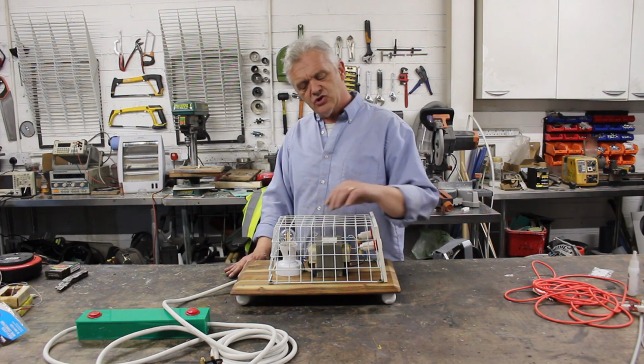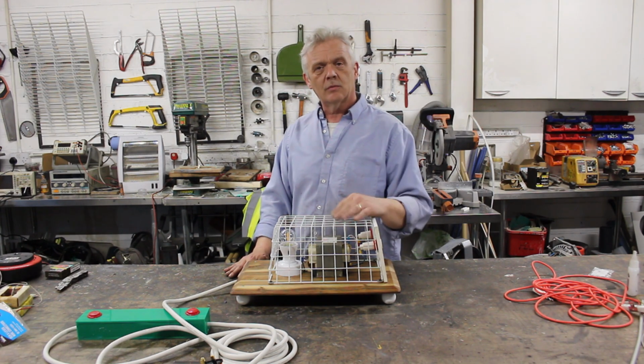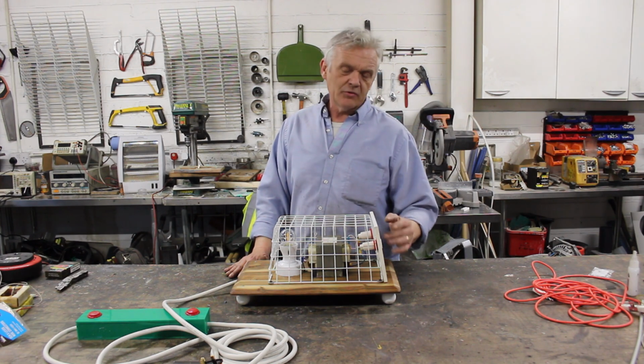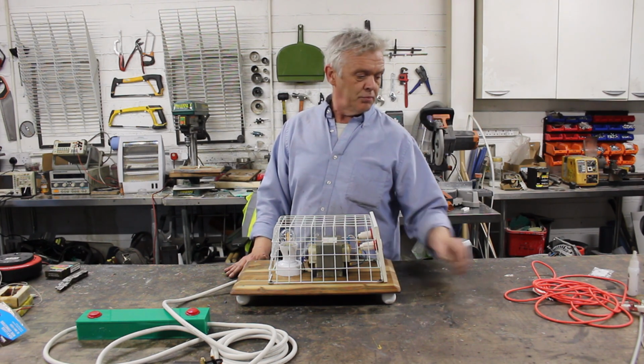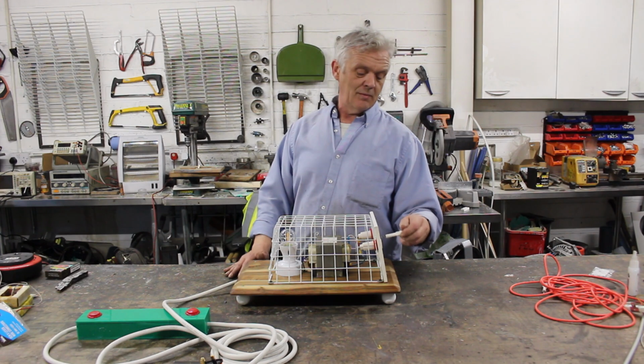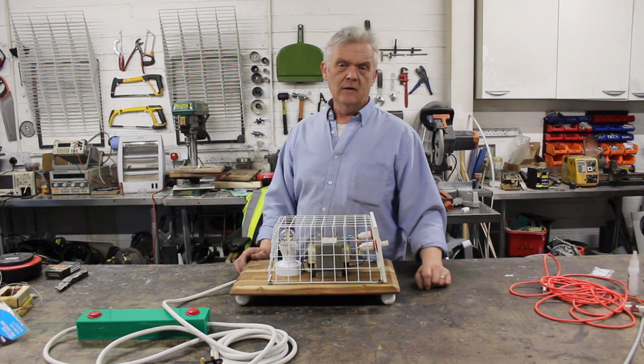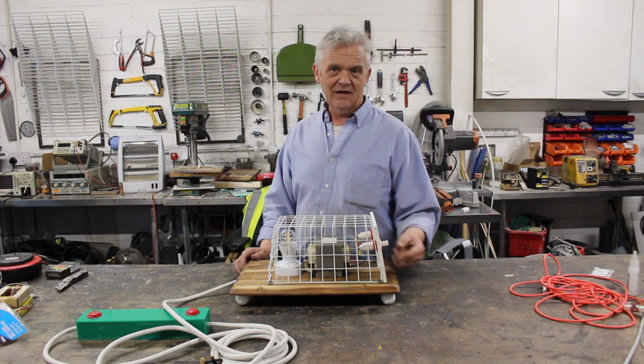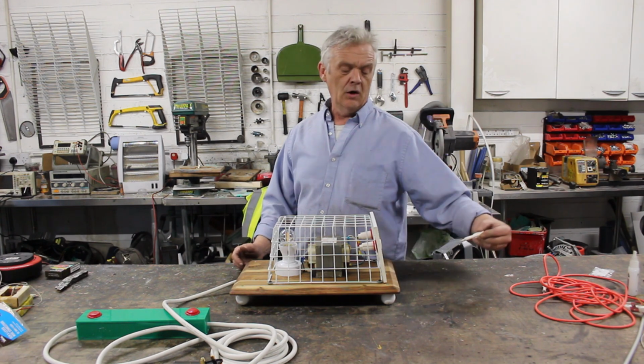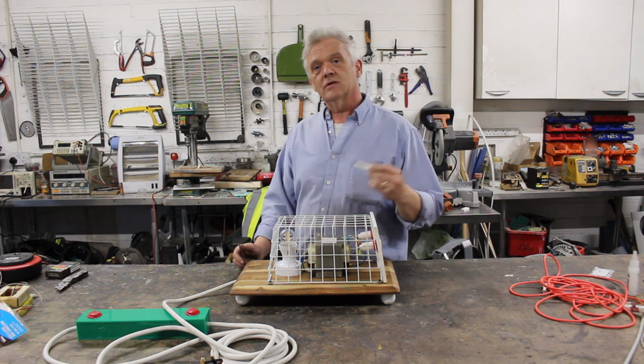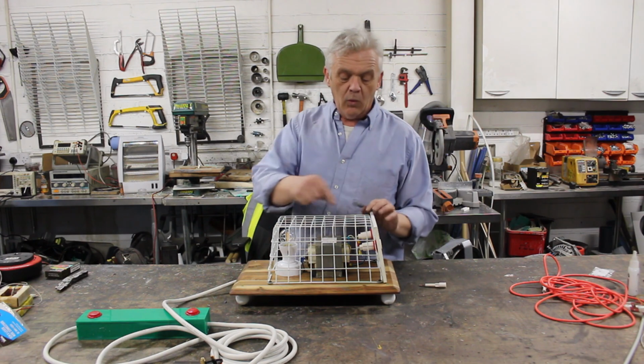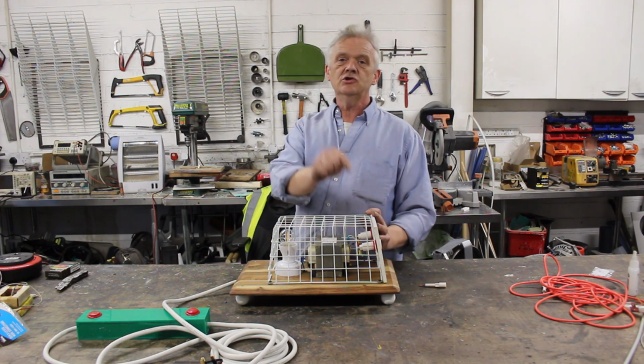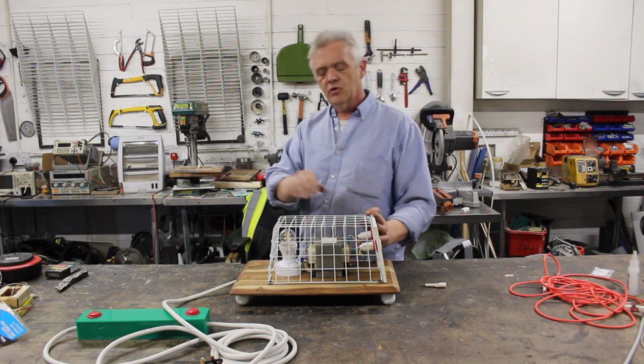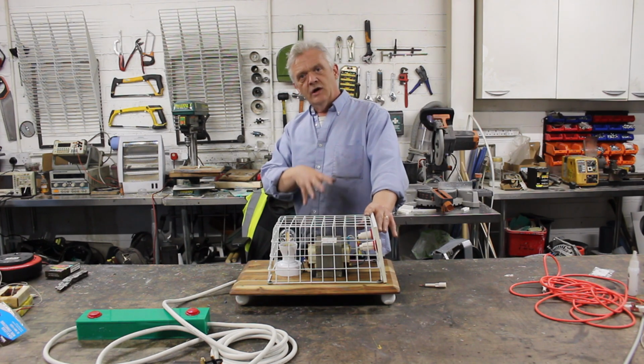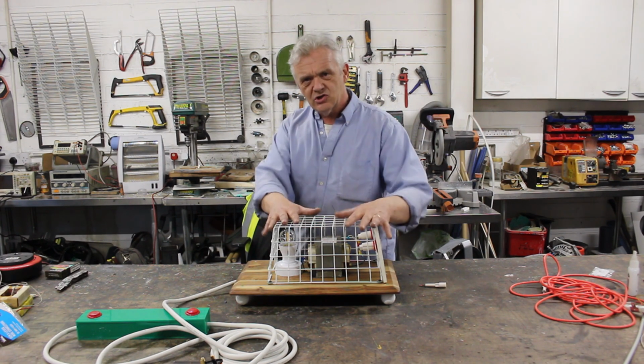They're all properly made with spade connections, but they're not under stress, and that's why that's important. If you've got your wires straight on here and you give them a tug, you may well break them. Here, with the proper termination, you're going to pull out this connector, because remember that goes in there so you can attach your leads to do your work. If you pull it, it'll pull straight out and won't do any harm, but it won't break that junction, because there's no stress on the junction. So it's tightly made, it's strongly made, you're isolated from it.